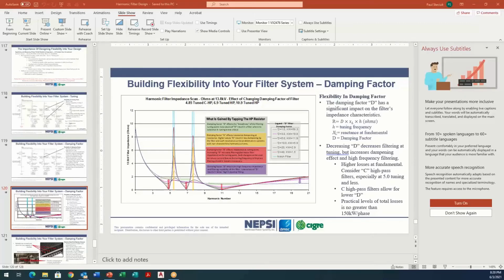So remember, the shunt reactors will not interfere with the impedance network from a resonance standpoint. But if you need to do filtering, then of course you need to put some shunt inductive reactance in addition to the filter bank capacitive reactance.